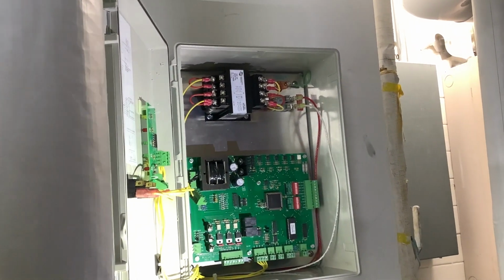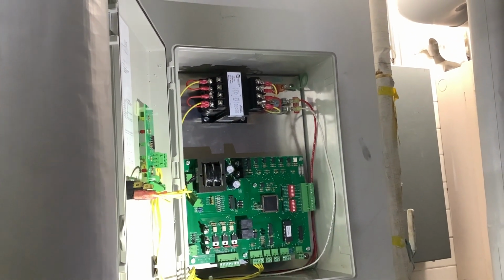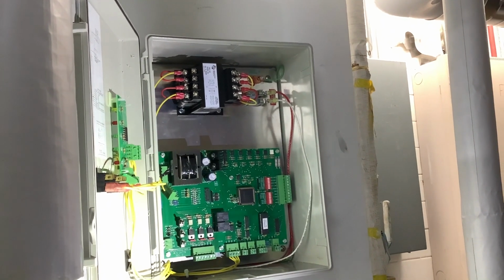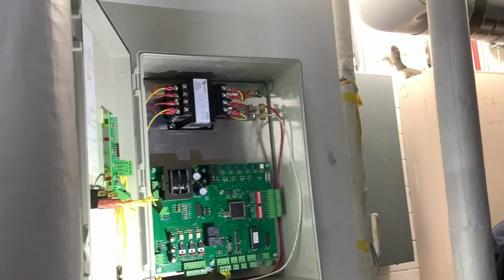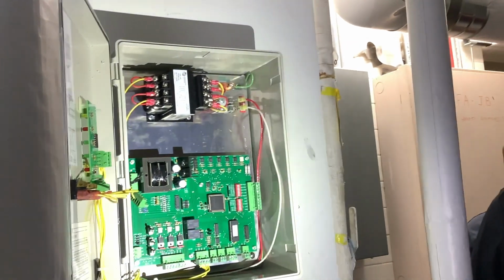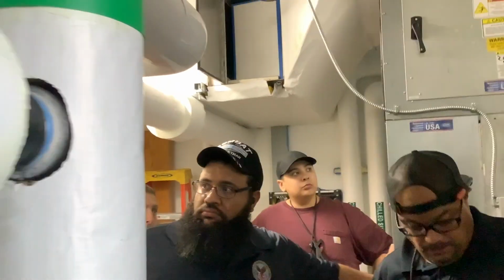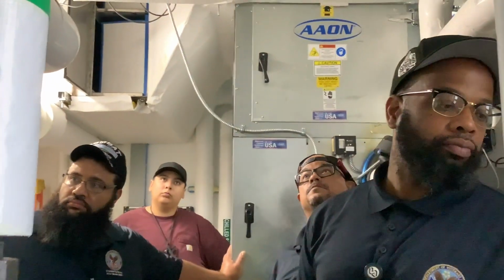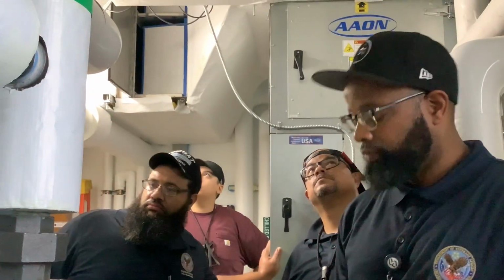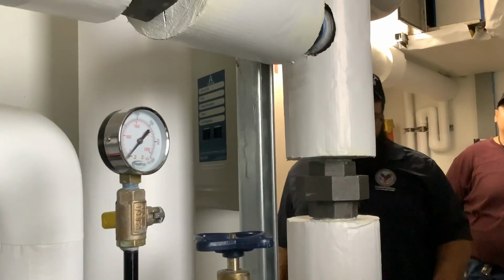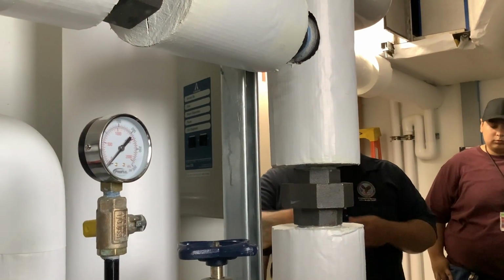All you're going to be able to do is turn it on, then drain it, fill it - that's it. That's how you test the solenoid, make sure it's dumping properly, because we don't want it overflowing and making steam. That's pretty much what the common calls are for. If we keep the barrel or the basin inside clean, they're a great piece of equipment.